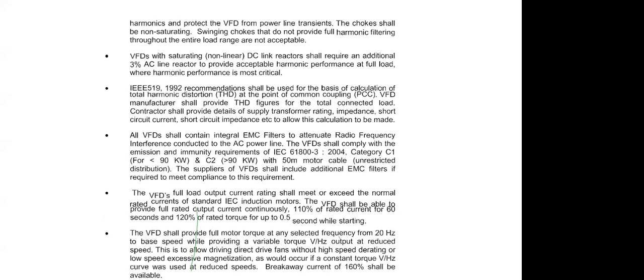IEEE 519 talks about the harmonics of the particular VFD or the particular system. Imagine a situation where we are using so many VFDs nowadays, like in the pumps. Even the secondary pumping system concept is gradually being phased out. We are converting to a primary variable system, so it's a single pumping system. Then we are using a variable compressor, centrifugal or screw. Next, we go to the AHU, which also uses a VFD. Now, if we go to a smaller installation, they are using VRF machines.